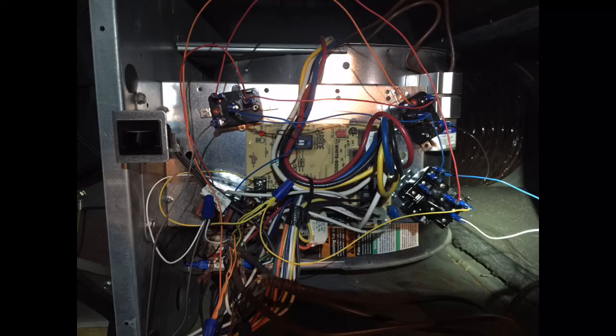Yeah, a lot of companies have done it that way, Mr. Heating Guy, and it typically does not cause a problem until you, like I said, get into systems that have got additional accessories dragging power down from the transformer in the system. If all you're doing is a humidifier as the only accessory added to it, you probably never have any significant problems, but every once in a while you can run into some issues. I appreciate your feedback on that.